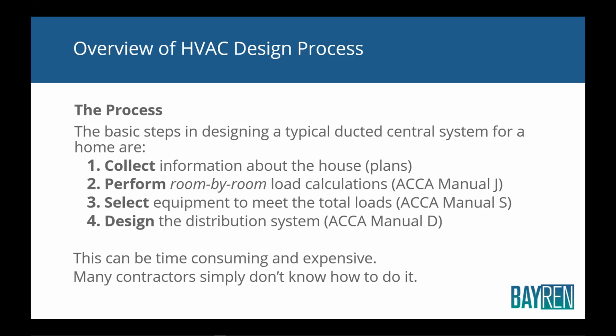Once you do your load calc, then you pick your equipment. That's Manual S, okay? So you select your equipment to meet the load. That equipment is going to have a certain airflow associated with it, assuming it's a ducted system. Okay, a certain airflow at a certain static pressure, at a certain resistance. Then you design your ducts to handle that airflow at that static pressure. So you design your ducts to provide a certain amount of resistance because the air handler table says this air handler will provide this many CFM at a certain amount of resistance. So then you have to design your ducts to not exceed that resistance so that you'll get your target airflow, okay? And that's what Manual D is all about.